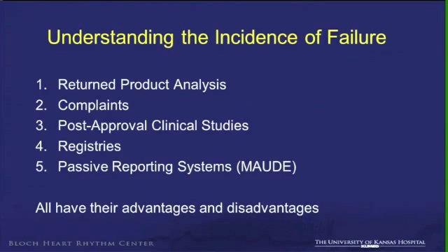There is return product analysis, which probably has the highest number in the denominator, but it's based on the products which are returned to the industry and analyzed. The good thing about that is you can actually analyze in detail the products which have been returned. The bad thing is that very few products are actually returned. That has changed over time. Now more and more products are being returned, so that is improving, but that underestimates the real incidence of failure.